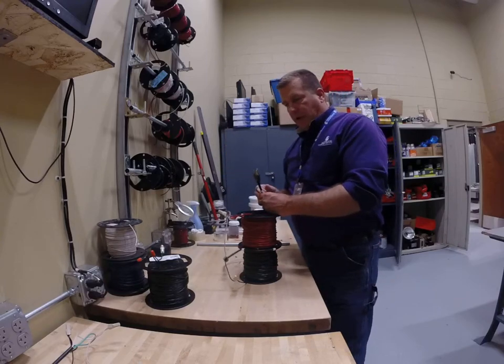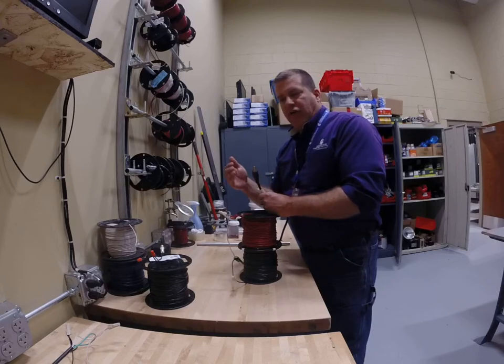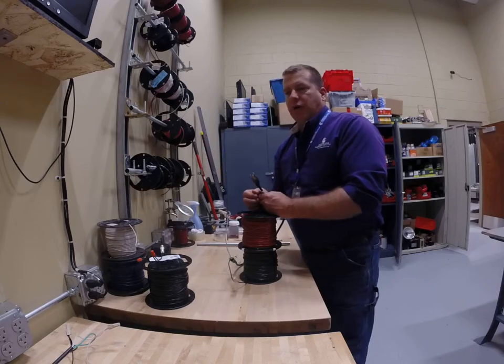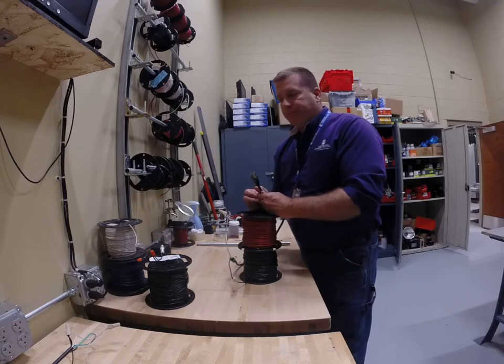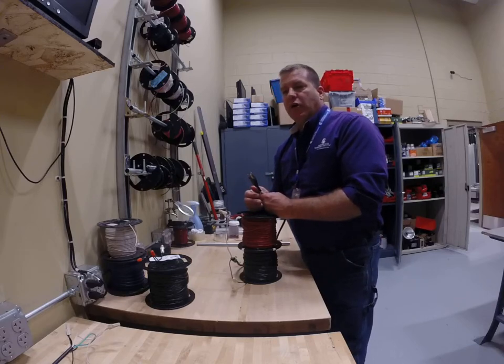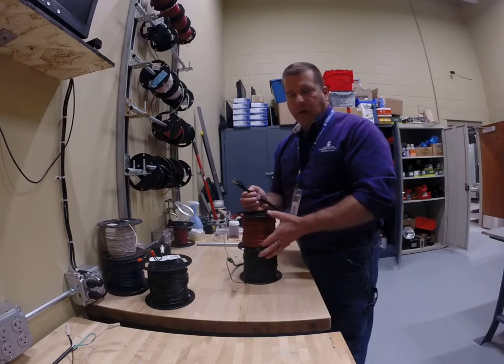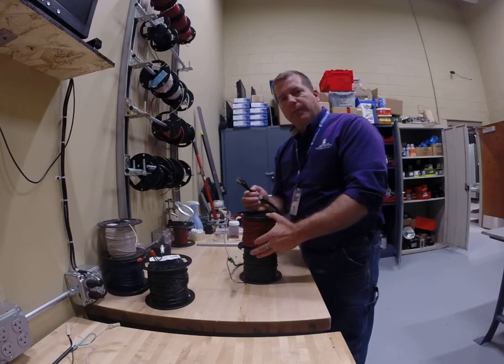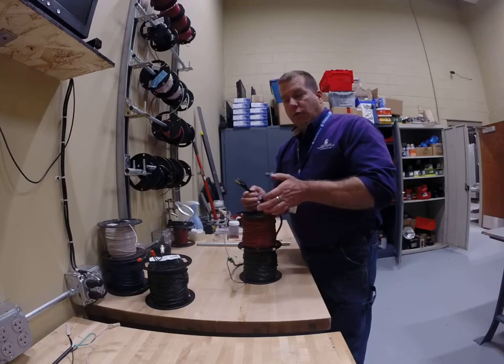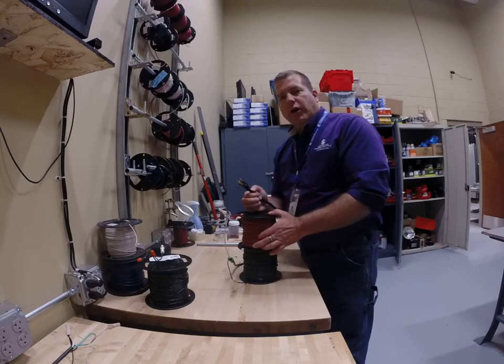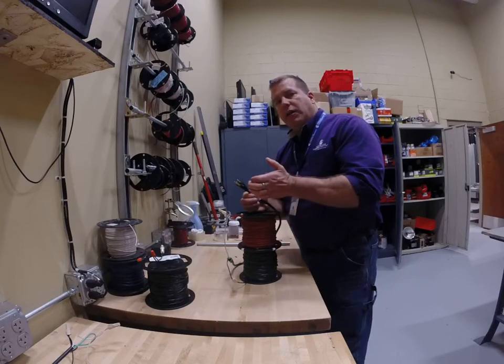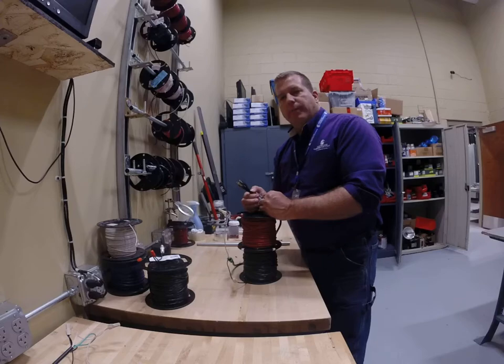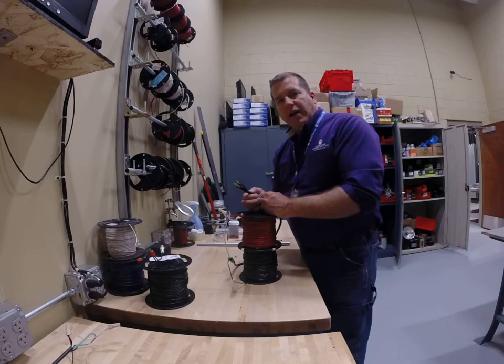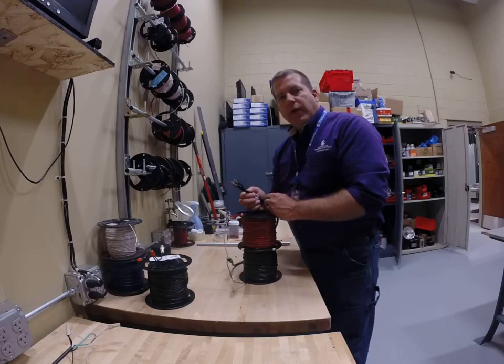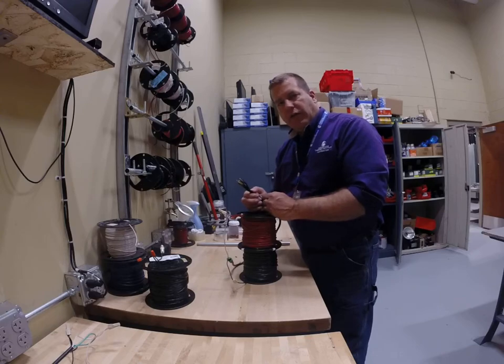Most people know that in order to prevent a short circuit, all of our electrical circuits are essentially a short circuit, but what prevents that short from tripping the breaker is resistance. As soon as we put a load into the circuit, it opposes the flow of current, limiting the amount of current so the breaker doesn't trip. We do that by sizing our branch circuits and overcurrent protective devices accordingly, then we go to the next job, hoping the breaker doesn't trip because we sized everything right.